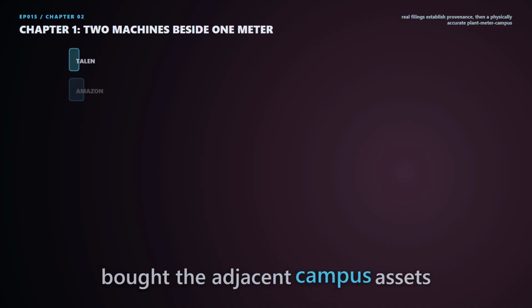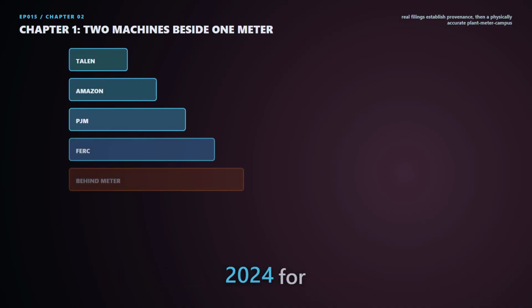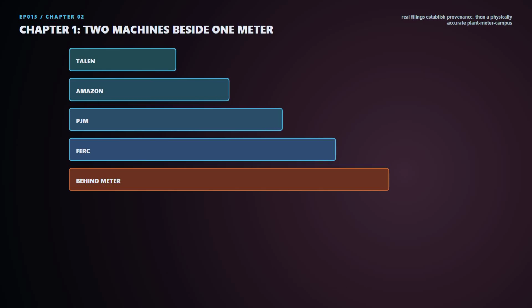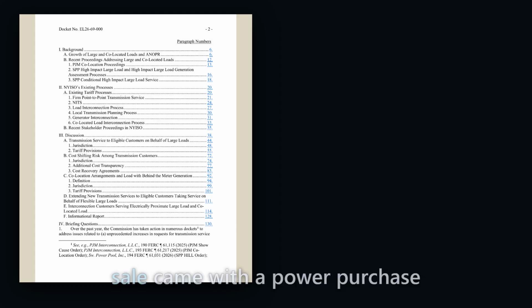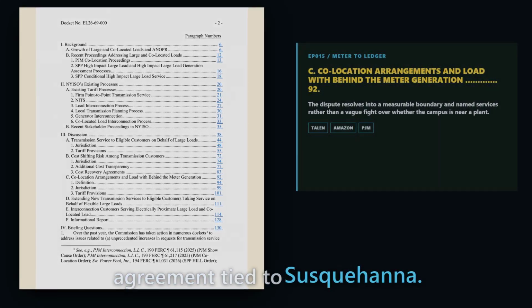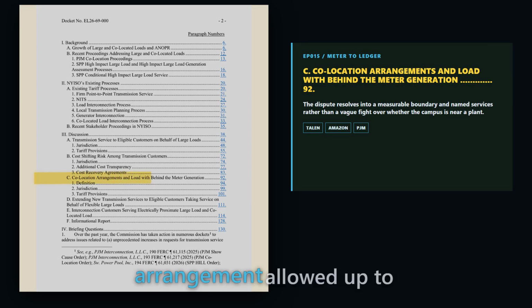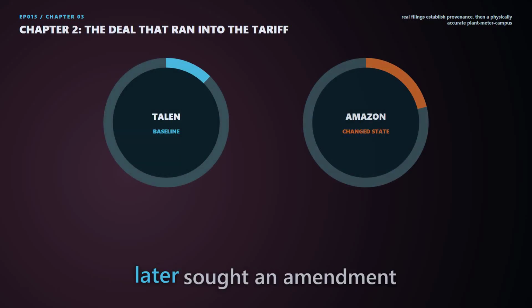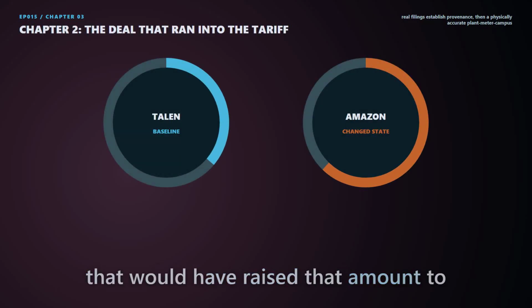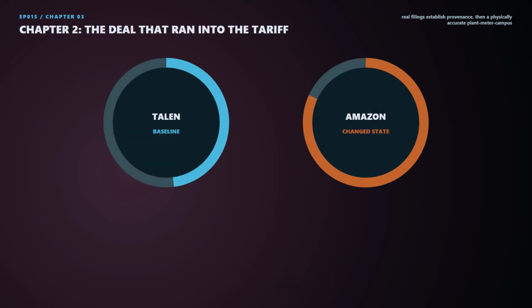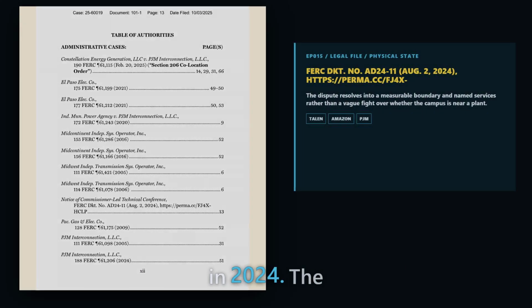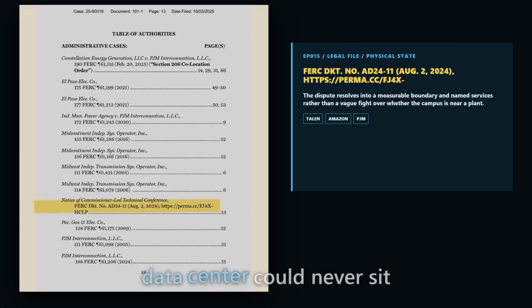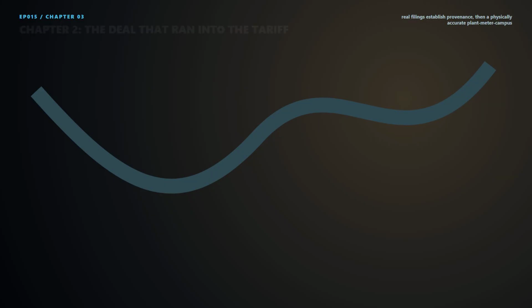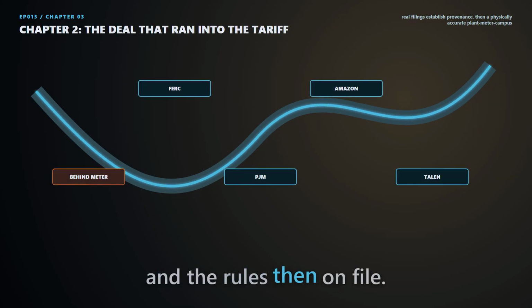Amazon bought the adjacent campus assets from Talen in March 2024 for a gross price of $650 million. The sale came with a power purchase agreement tied to Susquehanna. The original interconnection arrangement allowed up to 300 megawatts of campus load behind the plant meter. Talen, Amazon, and PPL later sought an amendment that would have raised that amount to 480 megawatts. FERC rejected the amendment in 2024. The rejection did not say a data center could never sit beside a generator. It turned on the specific agreement and the rules then on file.